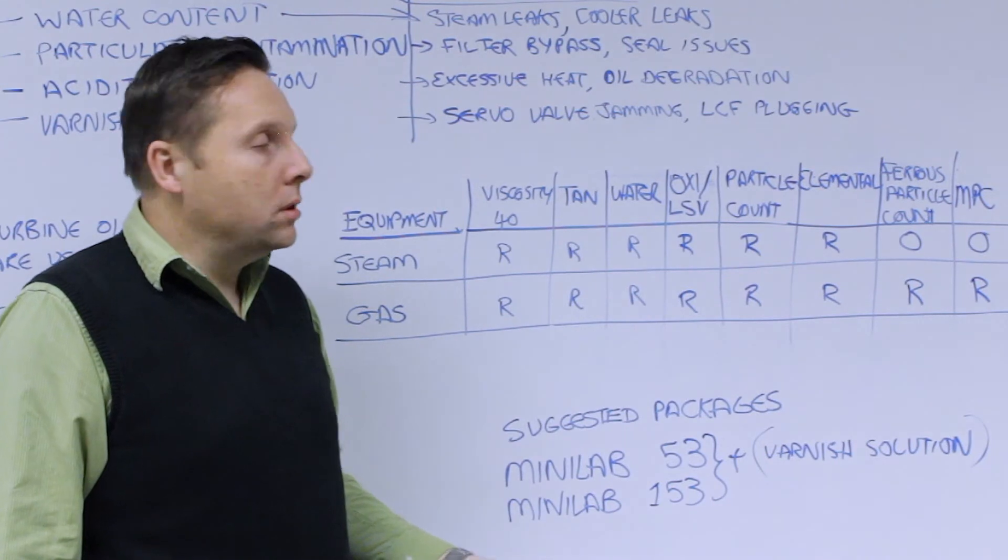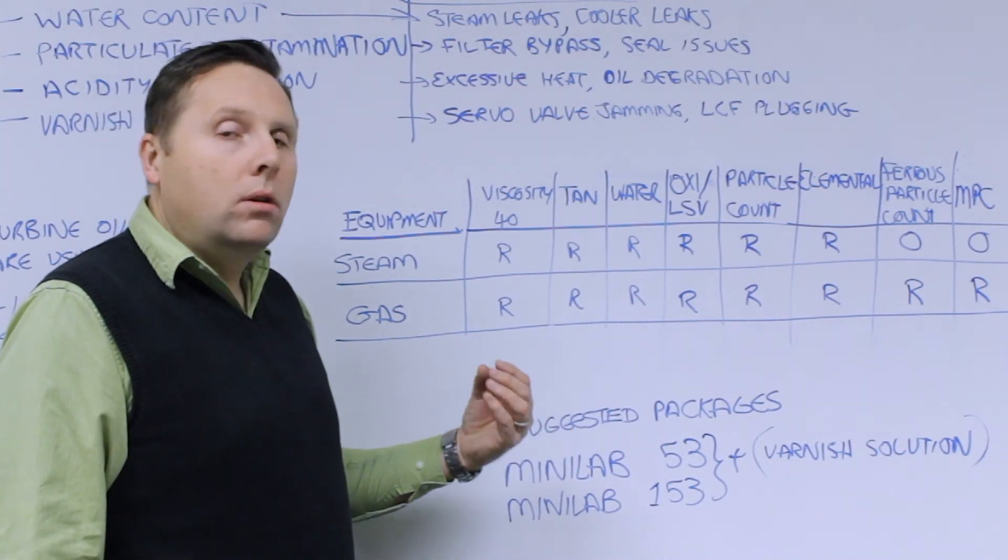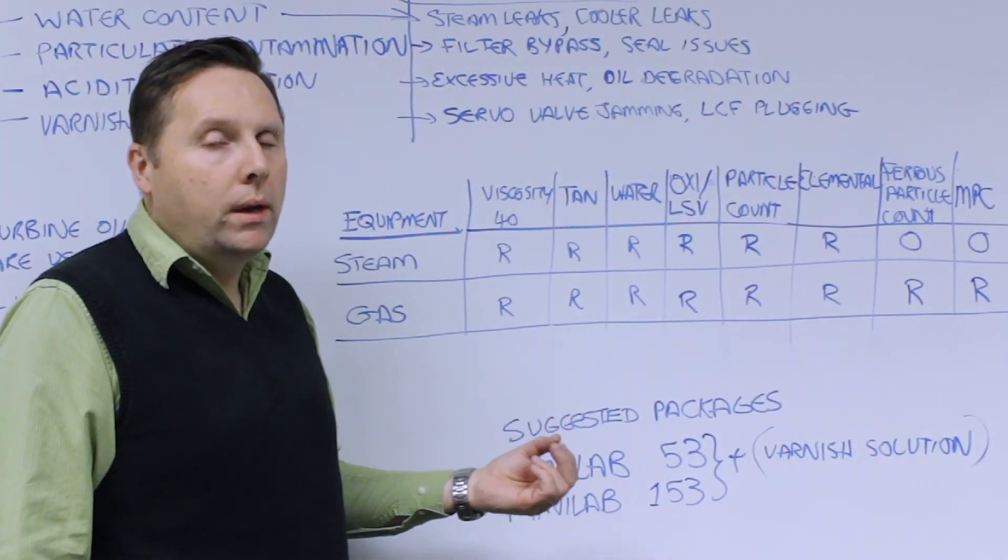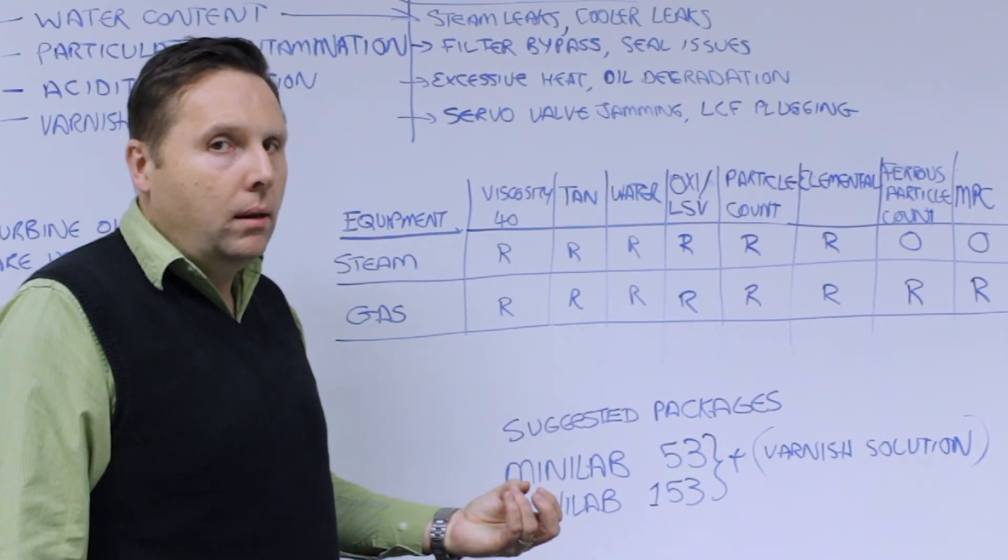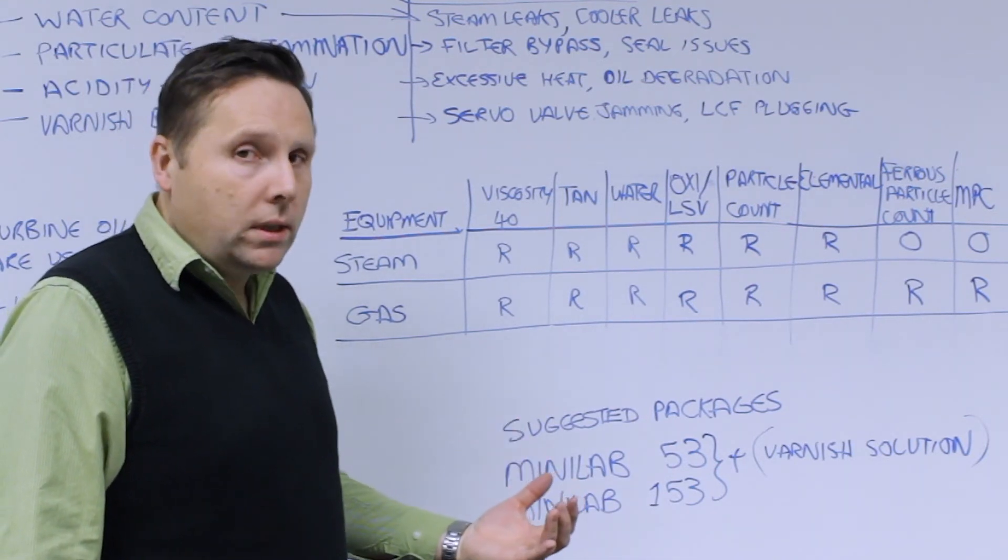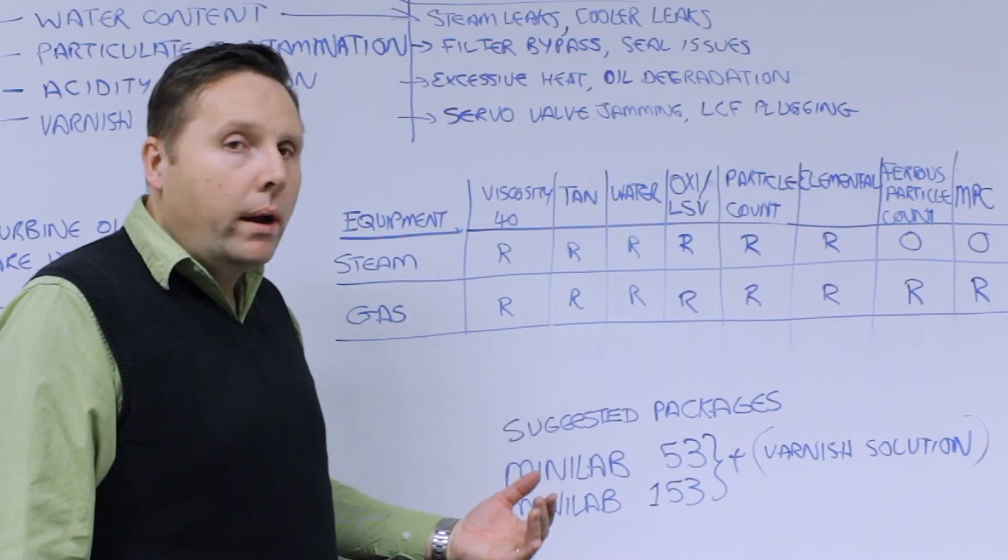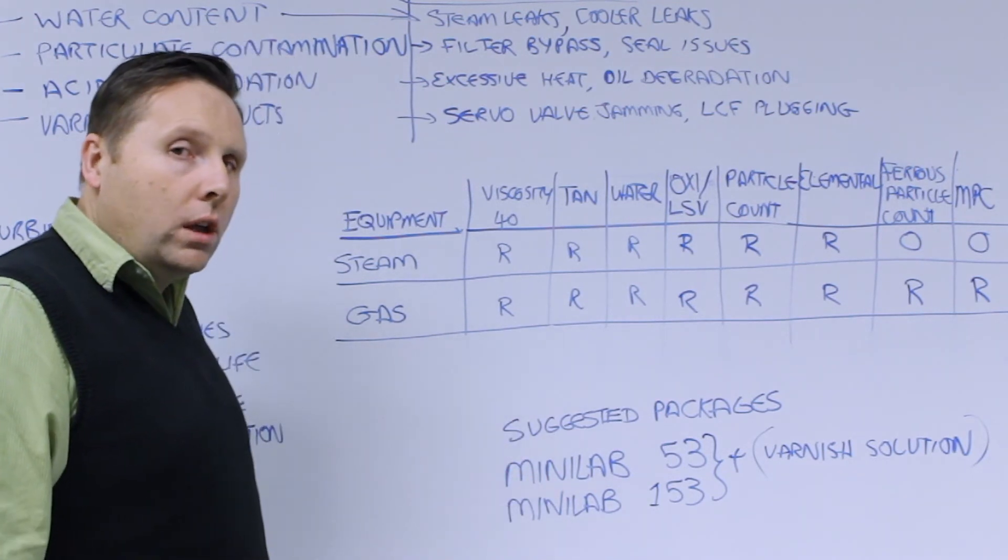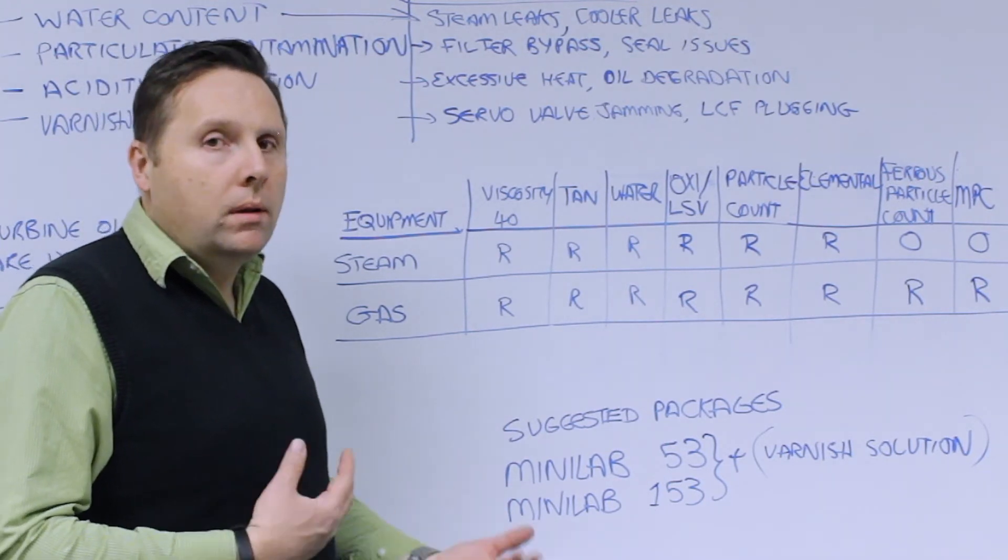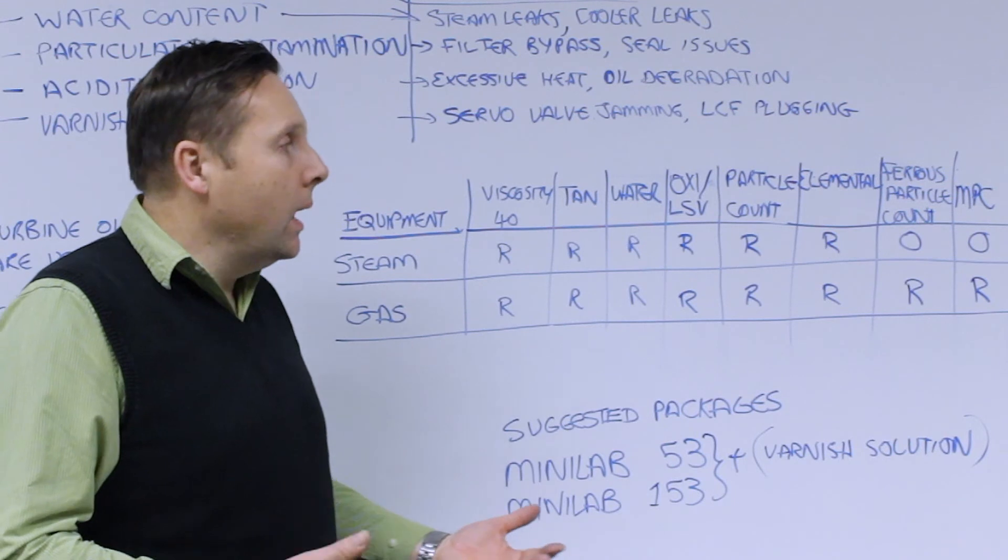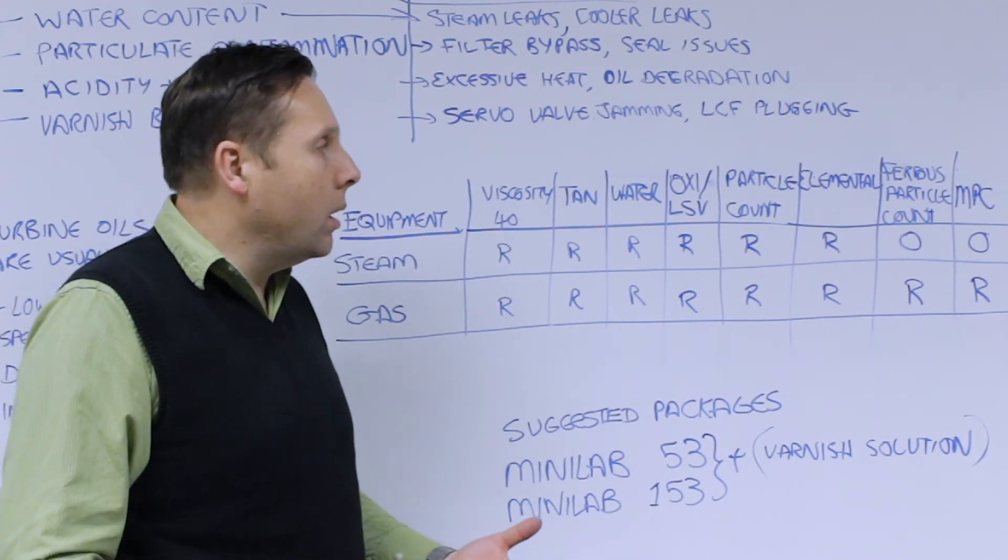Elemental is very important because what it does is it looks at trace amounts of wear debris that could be indicative of potential wear issues occurring in this system. Generally we don't expect to see wear but if there is wear because you're such a large volume of oil the dilution ratio is quite dramatic. So even small trace amounts of ppm like one or two ppm can indicate a wear problem.